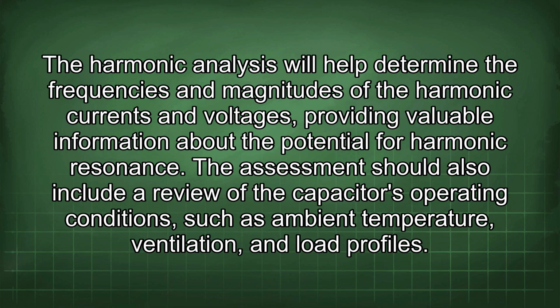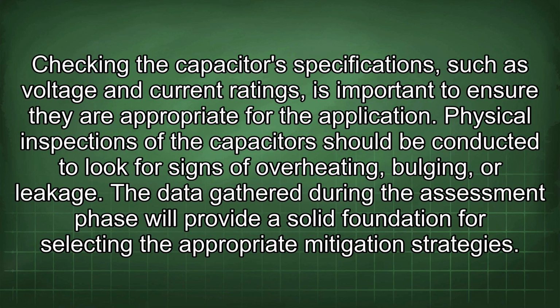The assessment should also include a review of the capacitor's operating conditions, such as ambient temperature, ventilation, and load profiles. Checking the capacitor specifications, such as voltage and current ratings, is important to ensure they are appropriate for the application. Physical inspections of the capacitors should be conducted to look for signs of overheating, bulging, or leakage. The data gathered during the assessment phase will provide a solid foundation for selecting the appropriate mitigation strategies.